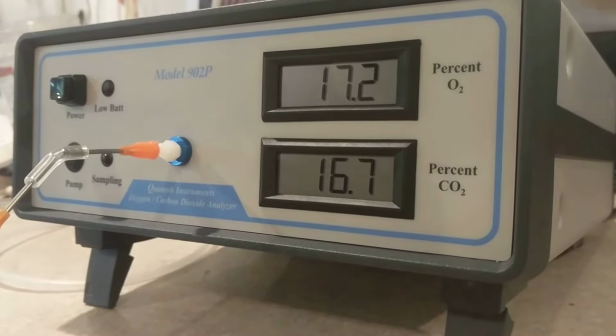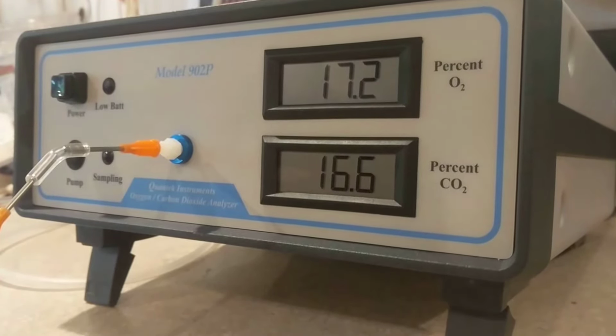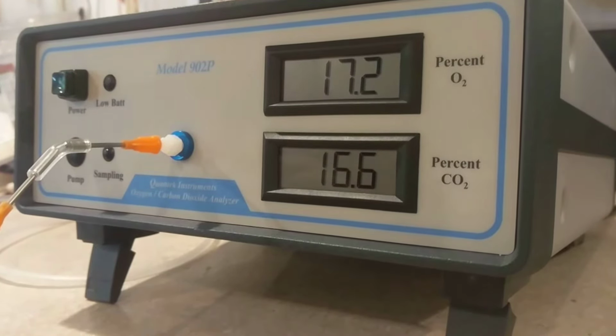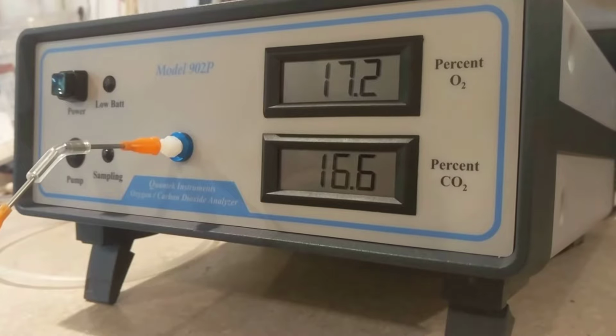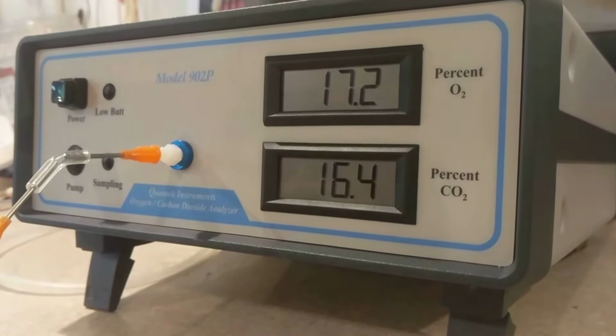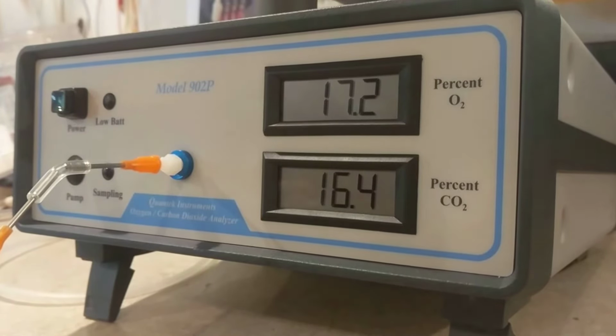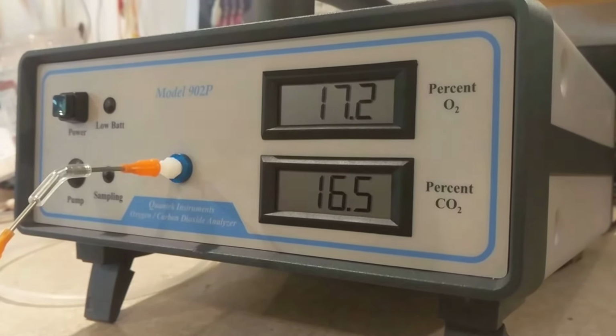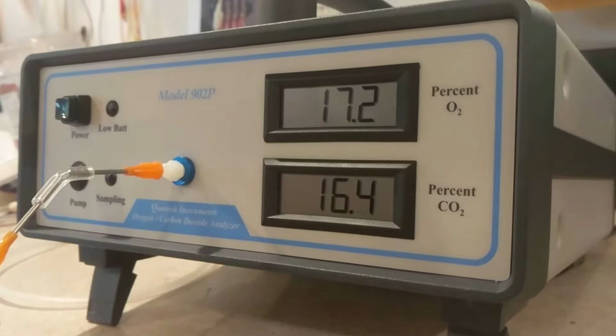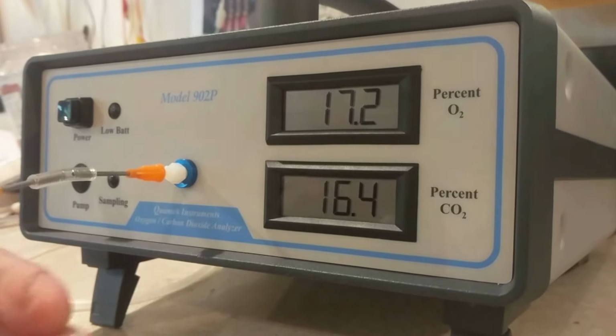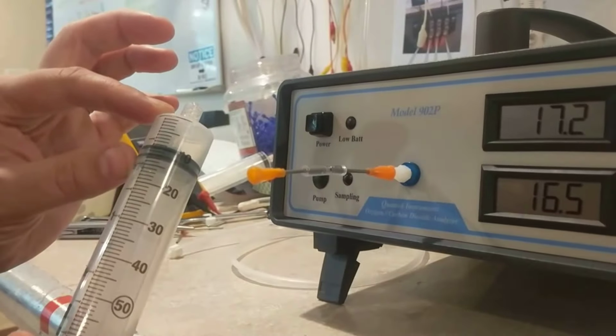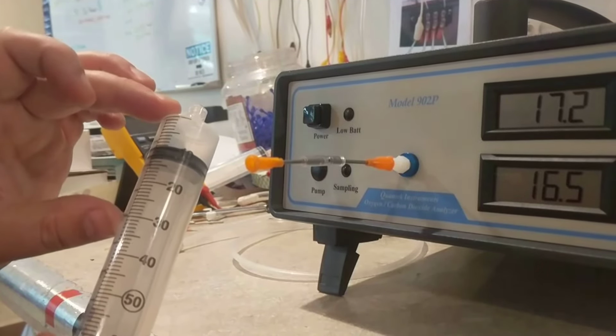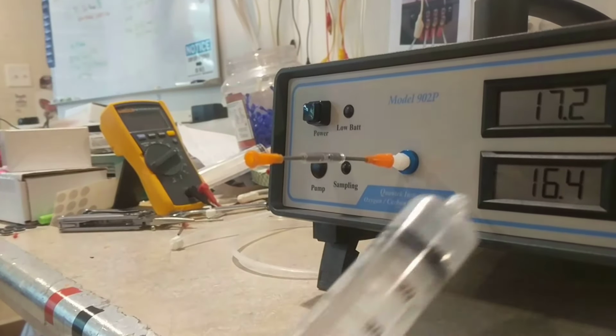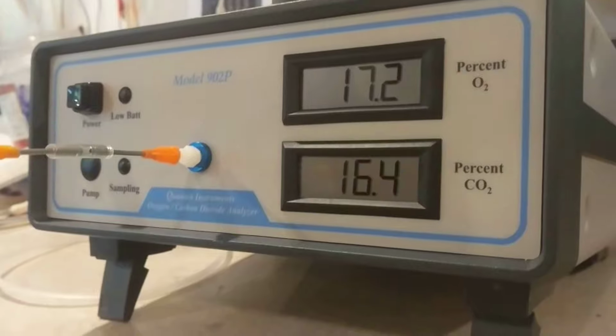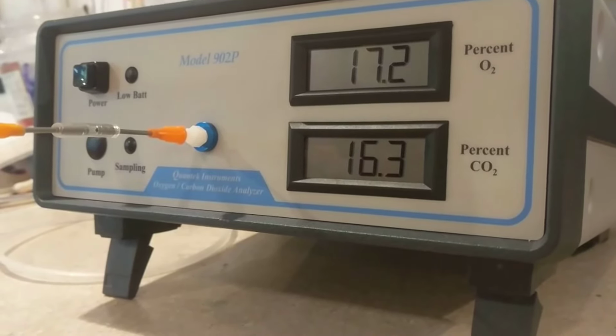And that's when you can adjust the CO2 span on the back. Again, it's always better to calibrate an instrument with a known CO2 concentration, such as 20% CO2 balanced in nitrogen. But as a last resort, if you have pure CO2 and want to check multiple points, you can do that. One other thing you can do is, instead of checking 10 cc's of pure CO2, you can also fill it halfway with pure CO2 and see if the CO2 ends up at 50%. That's it.